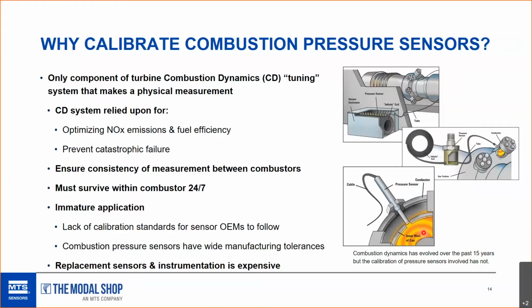Some of these pressure sensor manufacturers, not all of them, cannot calibrate at the relevant amplitudes for the application. So often when you install the transducer, it was not specifically tested for a real combustion dynamics application. And also the sensitivity tolerances are very high, 20%, maybe even higher. So there's a wide range of acceptable outputs. The onus is on the end user to make sure their instrumentation produces reliable, consistent data, and the best way to do that is by calibrating.